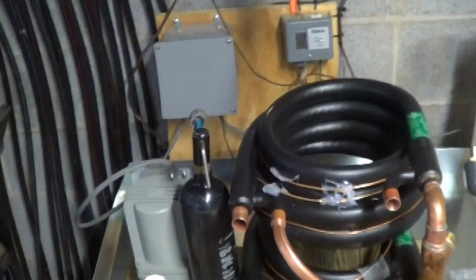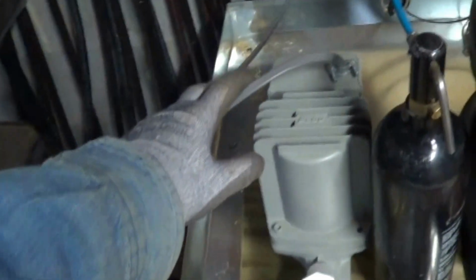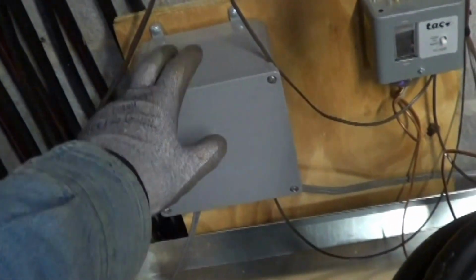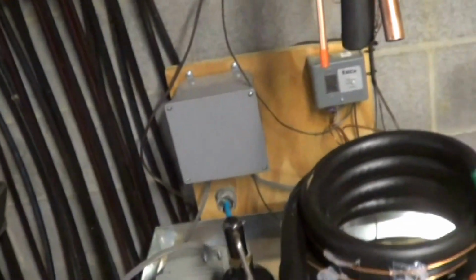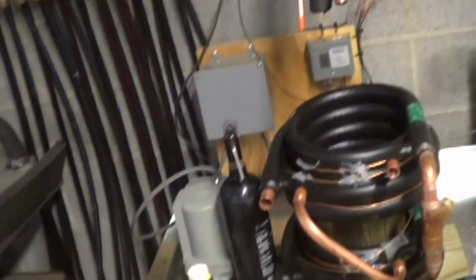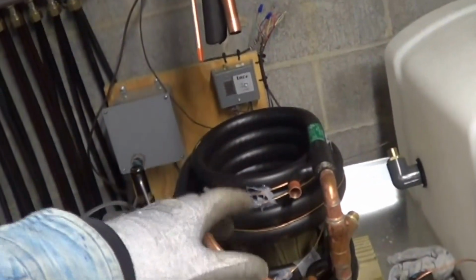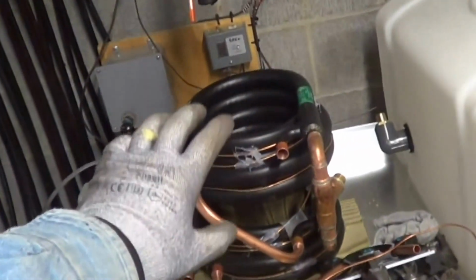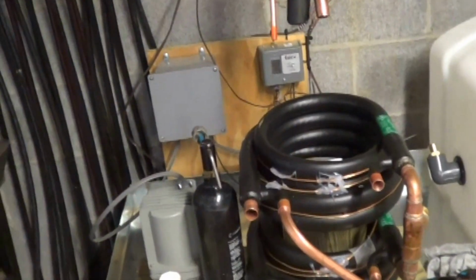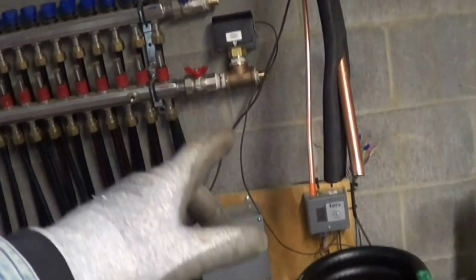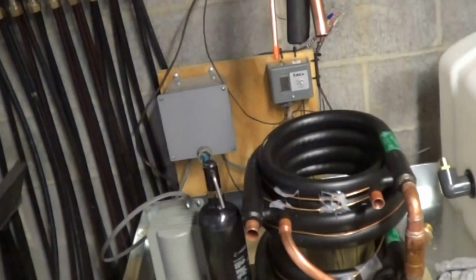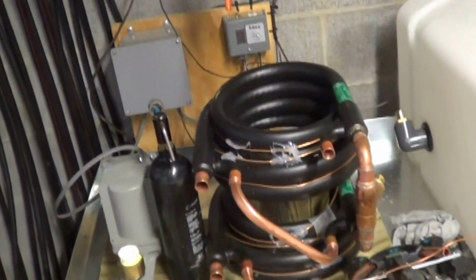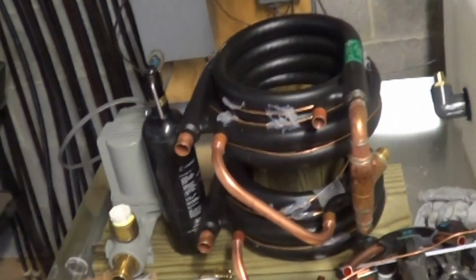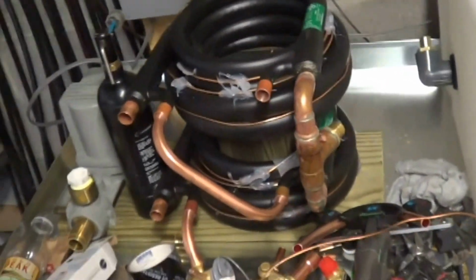The system's really simple. The pump is right here. It's just gonna come on, I got the relay, it just comes on with the green wire, just like a fan. So when the thermostat calls for green, turn on the pump. The interlock will make sure the compressor only runs when the heat exchanger has water. And so the interlock breaks the Y. And that's it, and just runs like a normal heat pump. It'll do its defrost, so it'll run in cooling mode.